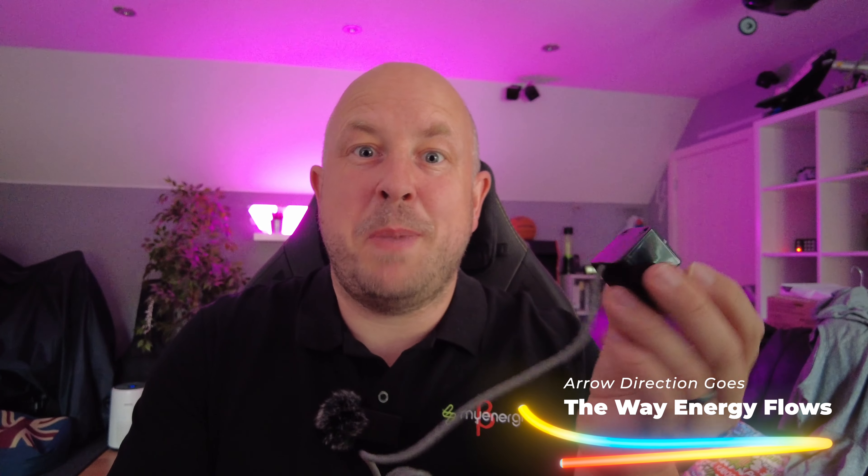You just have to check the direction — there's a little direction arrow on the back. You clip that over and it does a couple of things: it produces residual power through the cable to power the device, so you don't need any additional mains. It also enables the Zappi and the Eddi to have information from the grid. You need at least one CT clamp from a grid perspective, and both the Eddi and Zappi come with one in the box. As an optional extra you can connect a CT clamp to your solar and also to your battery.